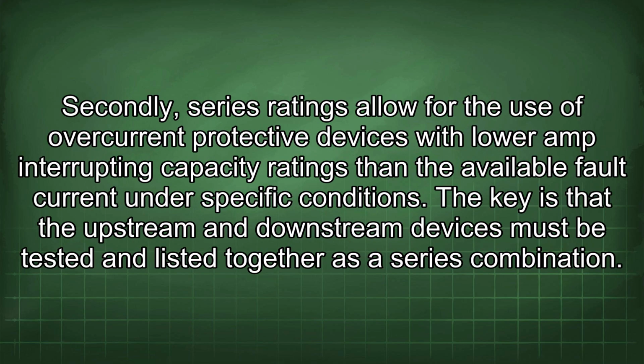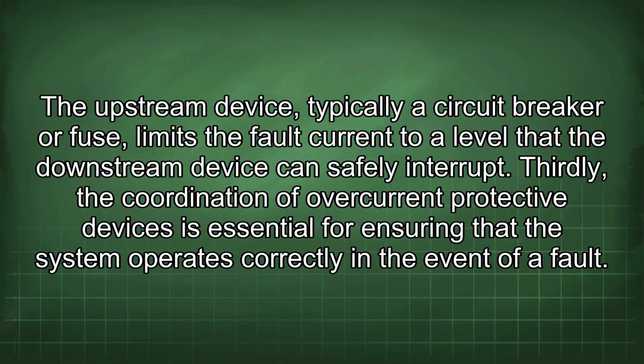Secondly, series ratings allow for the use of overcurrent protective devices with lower amp interrupting capacity ratings than the available fault current under specific conditions. The key is that the upstream and downstream devices must be tested and listed together as a series combination. The upstream device, typically a circuit breaker or fuse, limits the fault current to a level that the downstream device can safely interrupt. Thirdly, the coordination of overcurrent protective devices is essential for ensuring that the system operates correctly in the event of a fault.